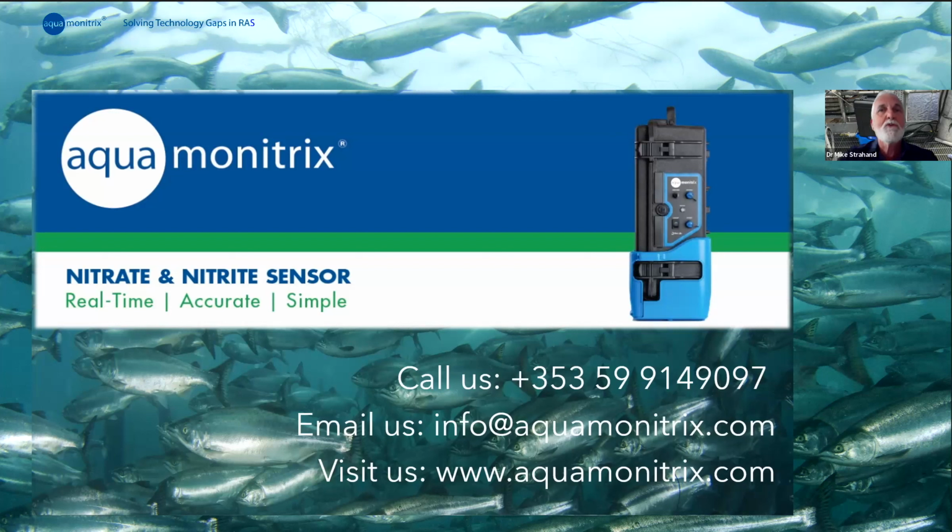One last question: operation range and accuracy. Just cover that one just before we sign off, Eoin, very quickly. Yeah, so the range is a very broad range, low ppb levels all the way up to 500 milligrams per liter as NO3 for nitrate, and 0.05 all the way up to 100 milligrams per liter as NO2 for nitrite.